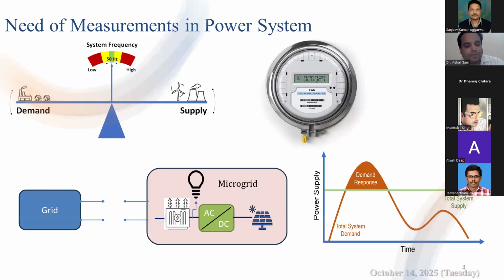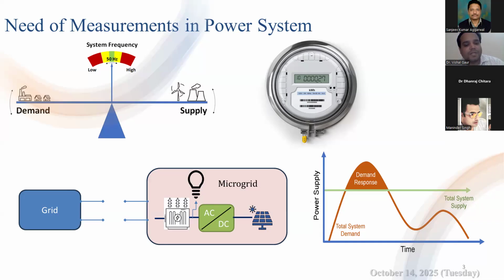Let us now focus on why measurements are absolutely essential in our power systems. If you look at these pictures, the first picture shows a balance between the demand and the supply. In any power system, generation must always match the demand. If the demand is increasing but supply doesn't, the system frequency drops below 50 hertz. And if supply exceeds the demand, the frequency rises. So we can say the system frequency is the very first indicator of system health. That's why continuous measurement of frequency is critical.